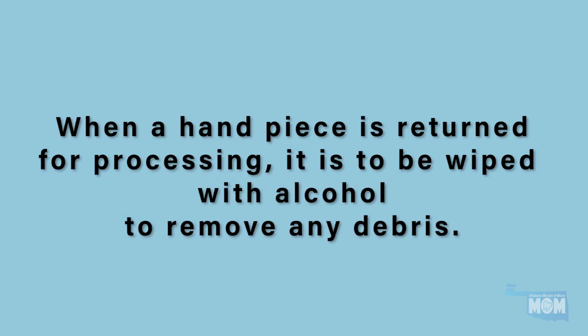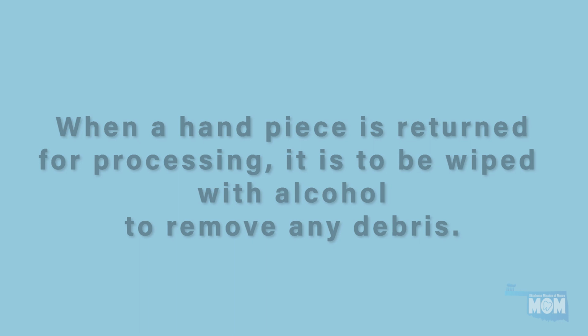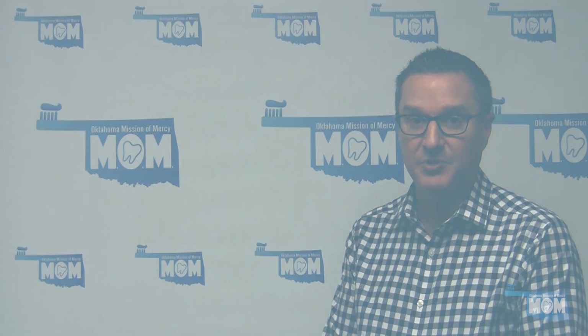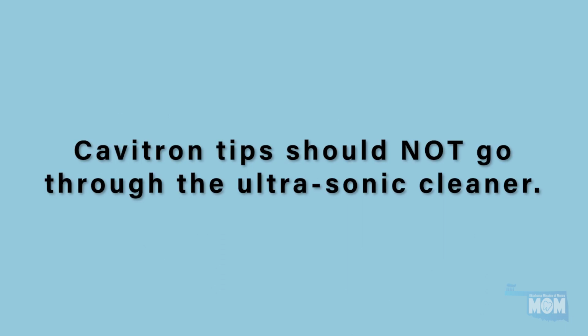When a handpiece is returned for processing, it is to be wiped with alcohol to remove any debris. They are then lubricated and bagged for sterilization. Cavitron tips should not go through the ultrasonic cleaner. Cavitron tips will be rinsed with water, any debris removed, dried, then bagged to be sterilized in the autoclave.